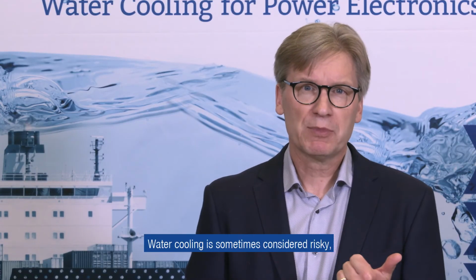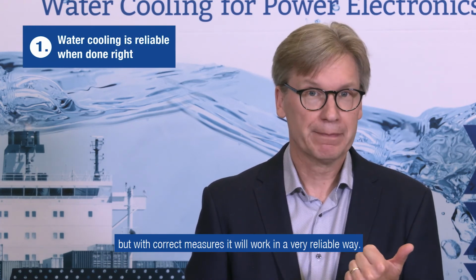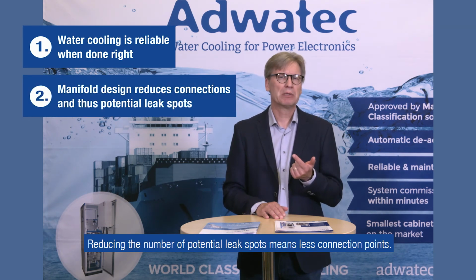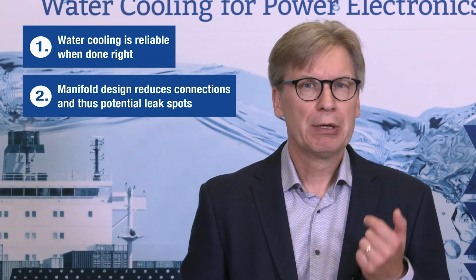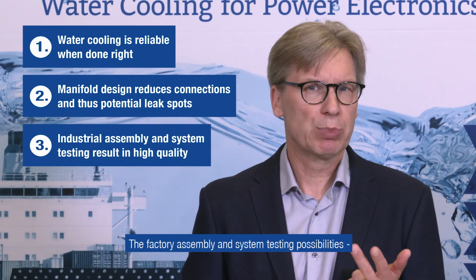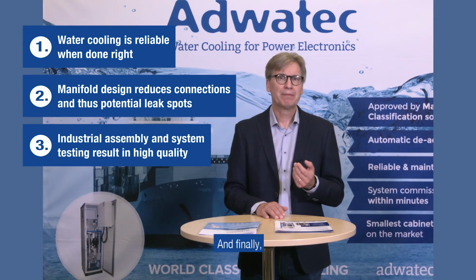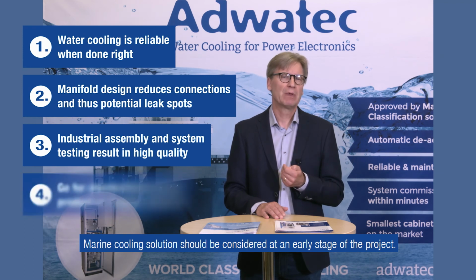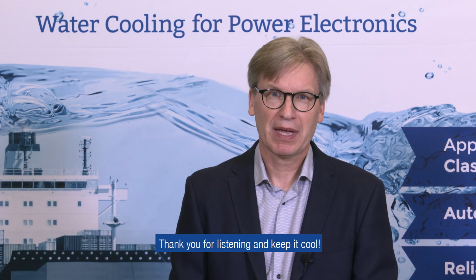Water cooling is sometimes considered risky, but with correct measures it will work in a very reliable way. Less is more. Reducing the number of potential leak spots means fewer connection points. Prefer manifold block designs. The factory assembly and system testing possibilities ensure the high quality of the cooling solution. And finally, marine cooling solutions should be considered at an early stage of the project. This way, standardized solutions can be used instead of tailor-made one-off creations. Thank you for listening and keep it cool.